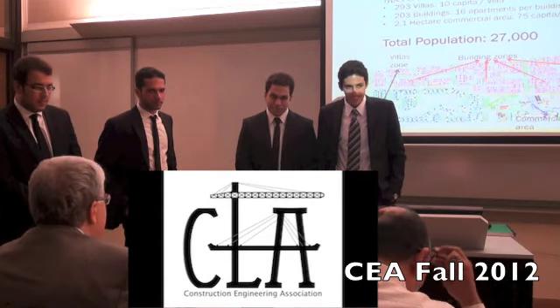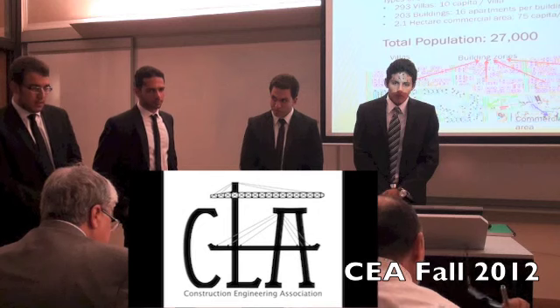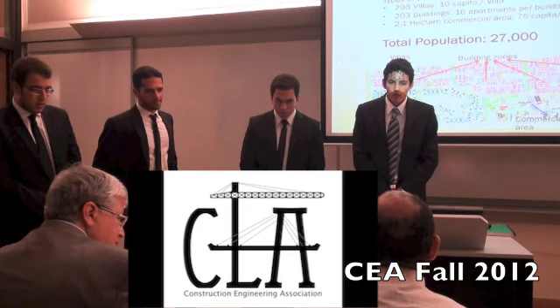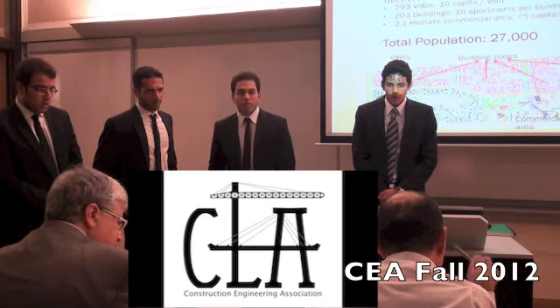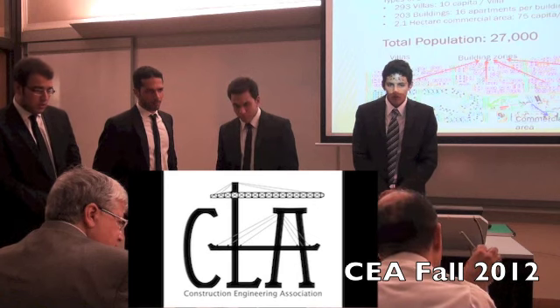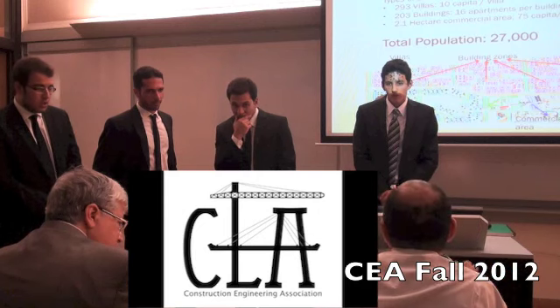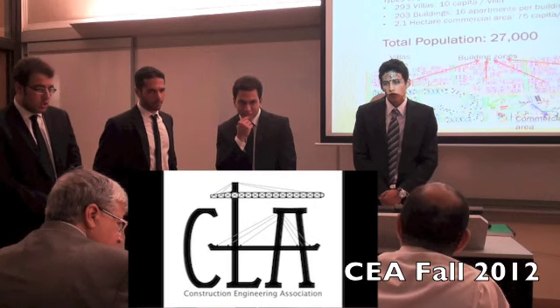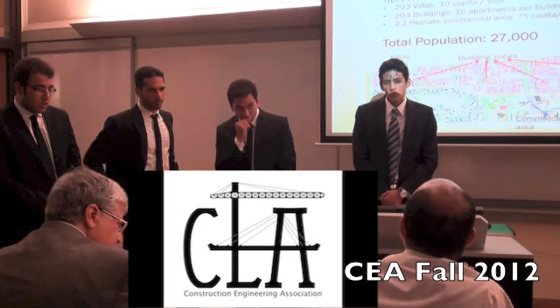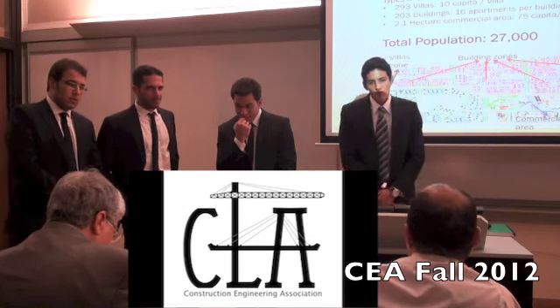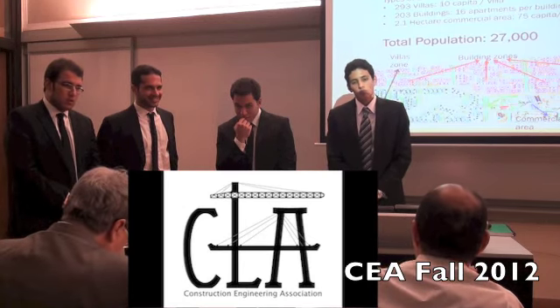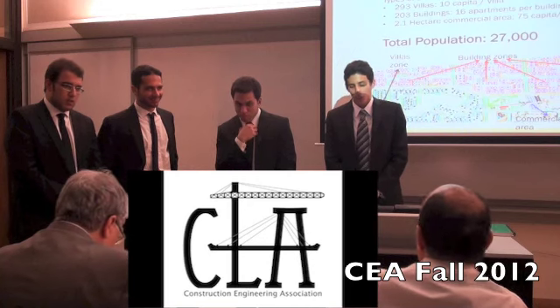Okay. One last comment. I was lucky to go and work with Dr. Ahmed Shafai on the design of an STP in Kuwait, which is half a million cubic meters per day. And you mentioned something which, if you hear it, you will have a heart attack. You said you are going to put the sewage treatment plant away from the complex in order to avoid the smell. If you have a smell from a sewage treatment plant, that means you failed. It shouldn't give you any smell. Even the sludge removal tank is contained. It doesn't smell. Okay, don't mention that.